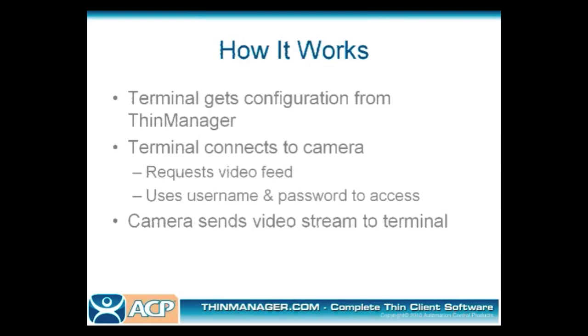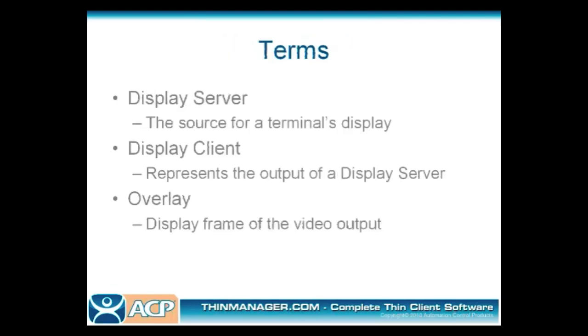The terminal will go to ThinManager and get its configuration. The configuration will tell it to run video from a specific camera, at a certain size and location. The terminal will connect to that camera over the ethernet, request the video feed, and will need the username and password of that camera to access it. The camera then sends the video stream to the terminal where it displays in the format you've selected. It's relatively simple and it works.